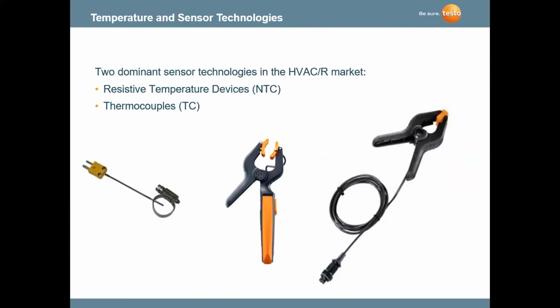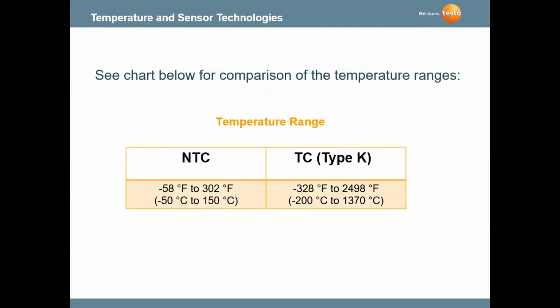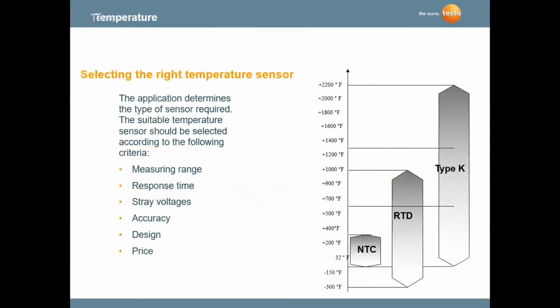So it's a technical term for as the temperature goes up, the resistance goes down. And the important thing to remember here is that NTC goes up to 302 degrees, whereas TC thermocouples can go up to 2,500 degrees. And typically in an air conditioning refrigeration application, NTC, we're at very low temperatures.